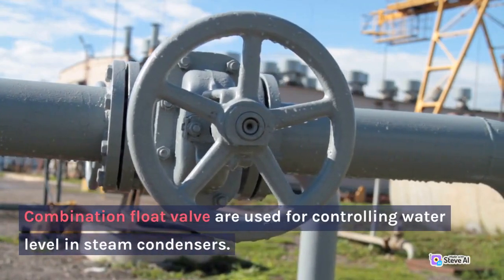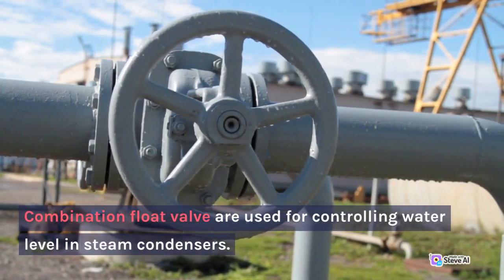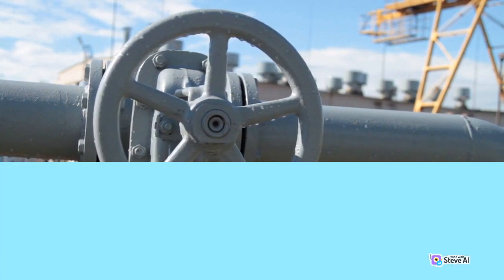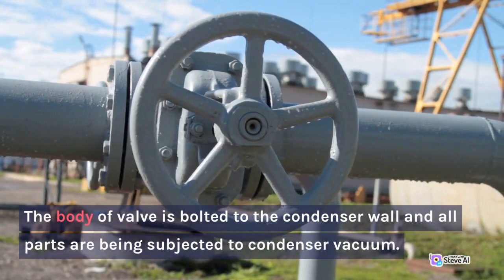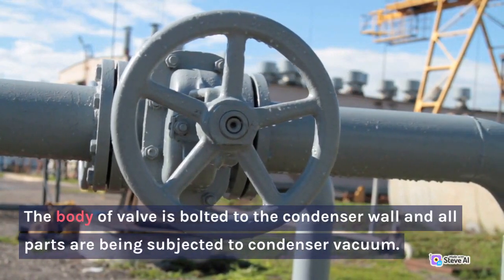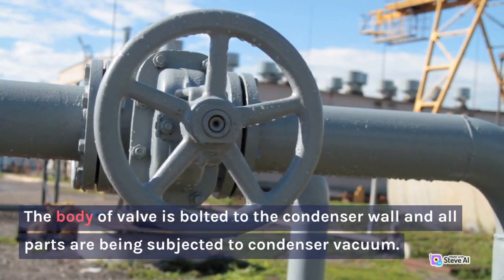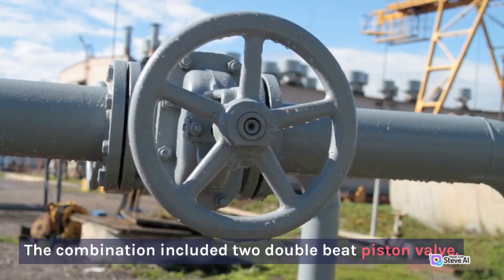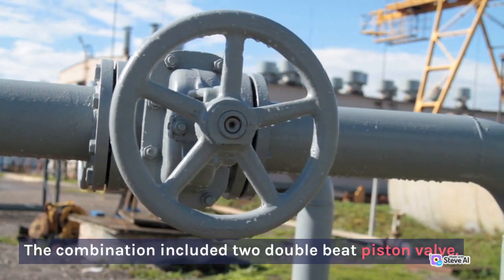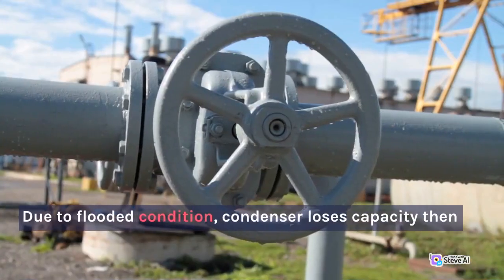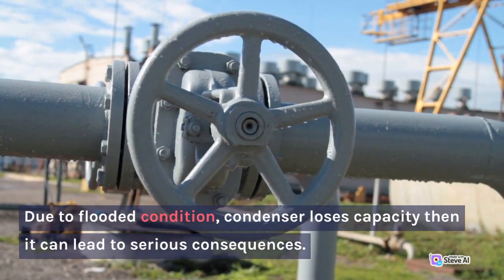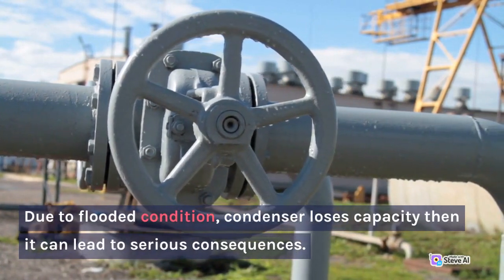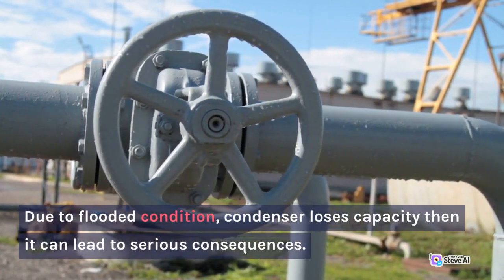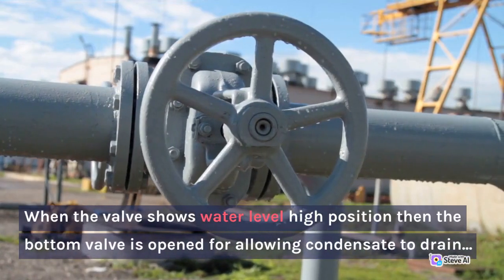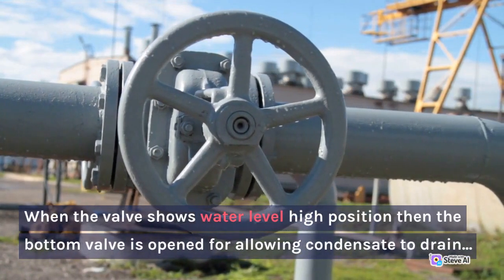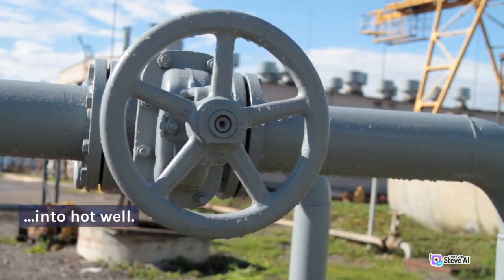Combination float valves are used for controlling water level in steam condensers. The body of the valve is bolted to the condenser wall and all parts are subjected to condenser vacuum. The combination includes 2 double beat piston valves. Due to flooded condition, the condenser loses capacity, which can lead to serious consequences. When the valve shows a high water level position, the bottom valve is opened for allowing condensate to drain into the hot well.